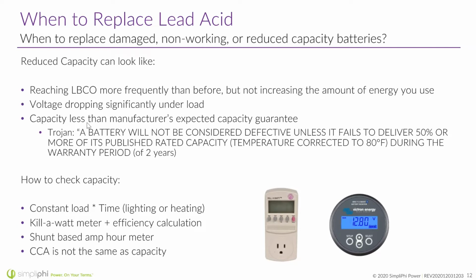So when I talk about reduced capacity, let's define this with the manufacturer's warranty. For one example, a Trojan battery will be considered defective only if it fails to deliver half or more of its published capacity during the warranty period of 2 years. So if you've owned the battery for 1 year and it delivers 60% of its rated capacity, that is still a good to go battery, at least as far as the manufacturer is concerned. Our warranty, on the other hand, is 80% of the rated capacity within a warranty period of 10 years.